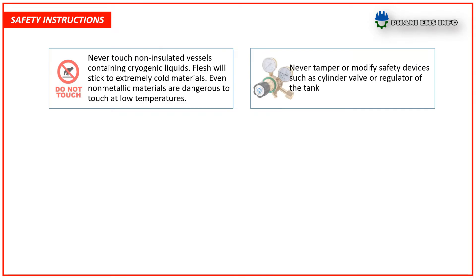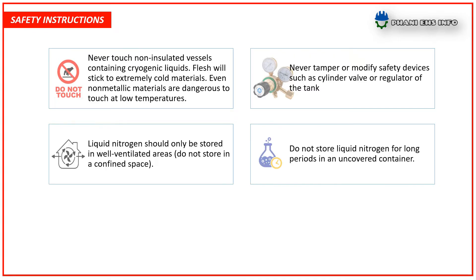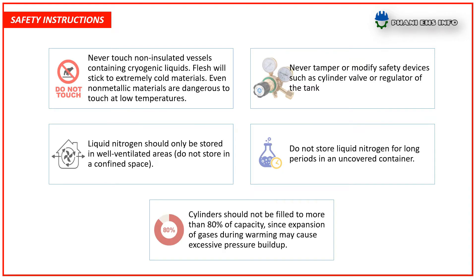Never tamper with or modify safety devices such as cylinder valves or regulators of the tank. Liquid nitrogen should only be stored in well-ventilated areas — do not store in a confined space. Do not store liquid nitrogen for long periods in uncovered containers.